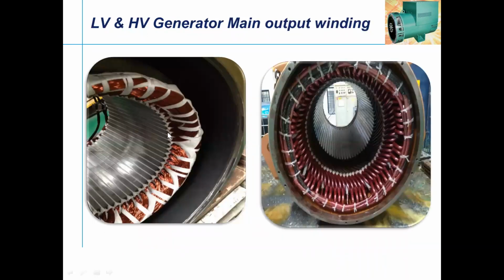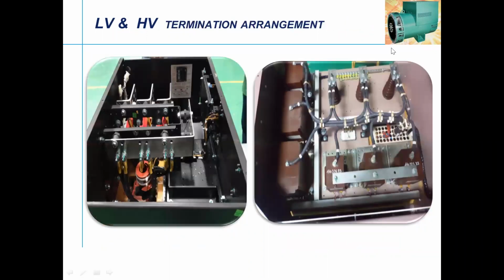This is again an LV winding, and this is an HT stator winding. You can see the phase separator and slot mouth we were talking about. This is the slot mouth insulation. This is the phase separator insulation. Overall, it is bound with the insulation tape. So this is the DE side of the winding, and the other is the NDE side of the winding. And here you can see the HT DE side of the winding, where the lead wires have been brought out and insulated, and brought to the terminal box for control wiring or for putting your CT.